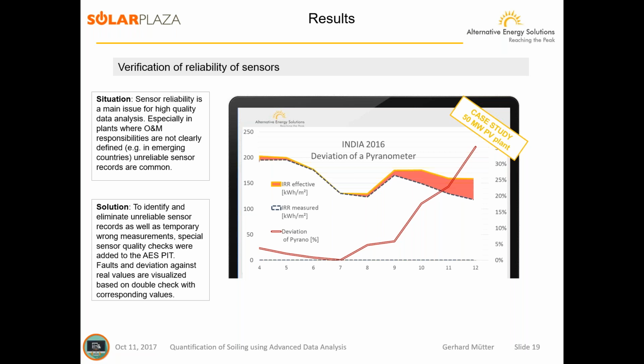They had no cleaning of the pyranometer, and as you see here on the baseline by month, in July there was monsoon, the yearly annual climate event, and the speciality is that the modules are really washed, and the pyranometer is also really washed. In December, they had 25% soiling on the pyranometer, and we were happy that they had a nice performance ratio, but it was just a lie, because the modules were not clean and the pyranometer was not clean.